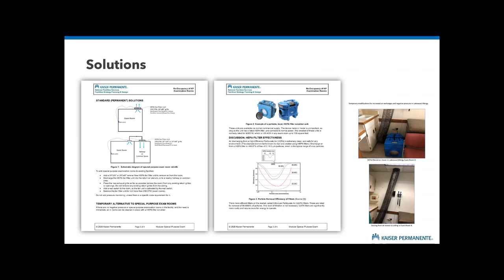We're also very much encouraging validation. Those pictures on the right are from last week. All you need to validate these is a $150 particle meter and a can of Aquanet hairspray. So we told them, yeah, great, go measure it. And when you measure the decay rate, you can report to your staff lead, hey, with this thing running, the room clears particles in 25 minutes.